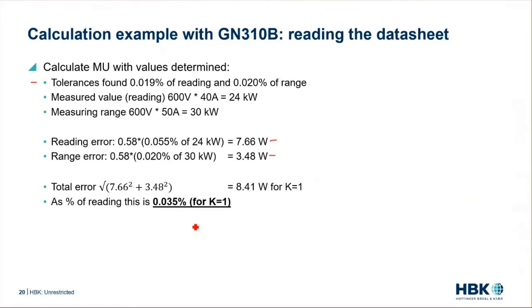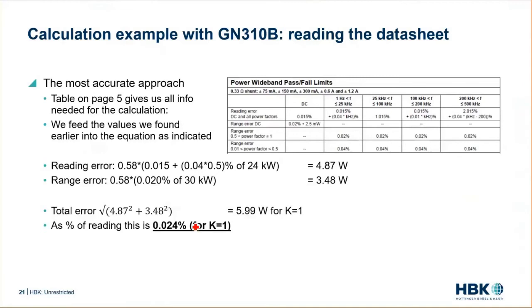A more accurate approach uses the table on page 5, which gives all the info needed for the full calculation. Feeding the values into that equation, the reading error is again 0.58 times the formula, taking the reading error for the relevant frequency, giving 4.87 watts. Doing the same for the range error and applying geometric addition, we get 5.99 watts or 0.024 percent, which is lower than what we calculated with the lookup table.